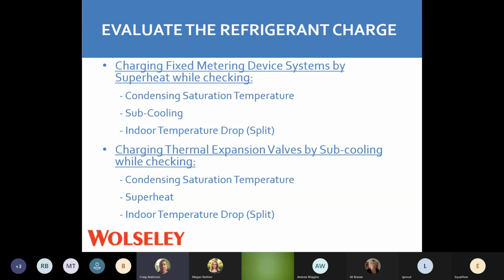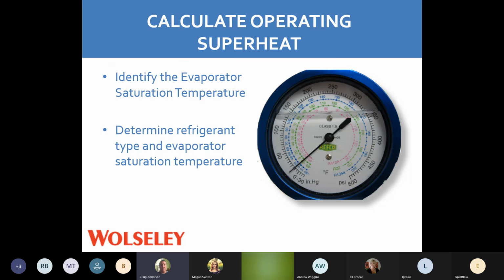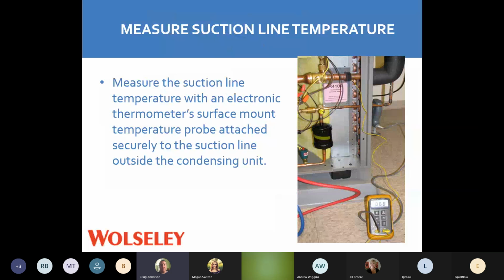Charging a TXV, we're still going to check our subcooling. So we're going to check our condensing saturation temperature, our superheat, and our indoor split between our return air and our supply. So identify the evaporator saturation temperature. Determine the refrigerant type that you're using and your saturation temperature. When you're looking at your gauges, your pressure is going to be on the outside of your gauges, and depending on what freon you're working on is going to tell us your saturation temperature. So we're going to need that temperature, plus the temperature that we've got off our suction pipe outside with our electronic thermometer.